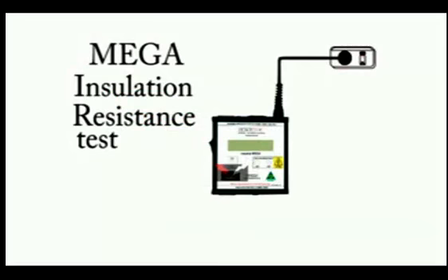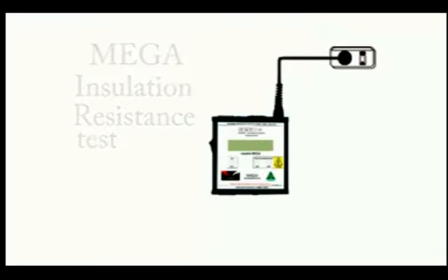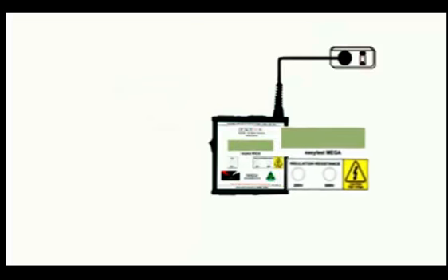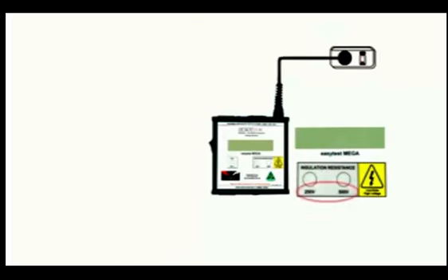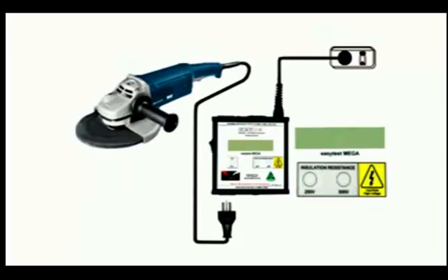When assessing the insulation of an appliance, the Mega enables us to check either leakage current in a run test or to check insulation resistance by applying a voltage across the insulation. Since an insulation resistance test will not power the device, that's what we'll use to get an initial assessment of more aggressive equipment like this big angle grinder, where it's more comfortable and possibly physically safer than to do a run test. Although it is industry best practice to perform a run test on any device with moving parts.